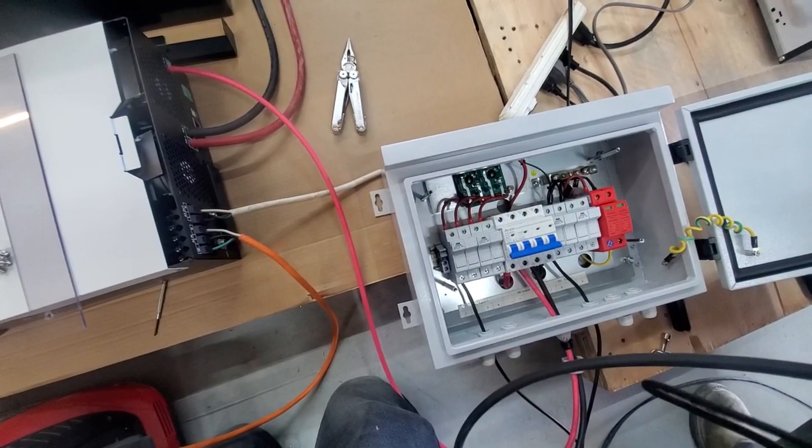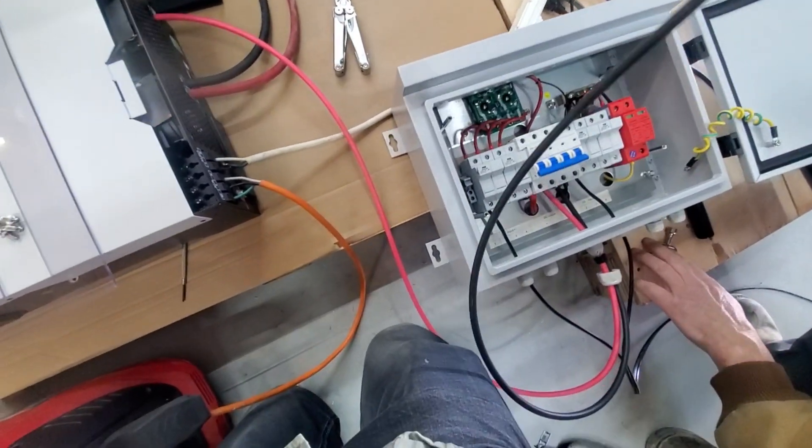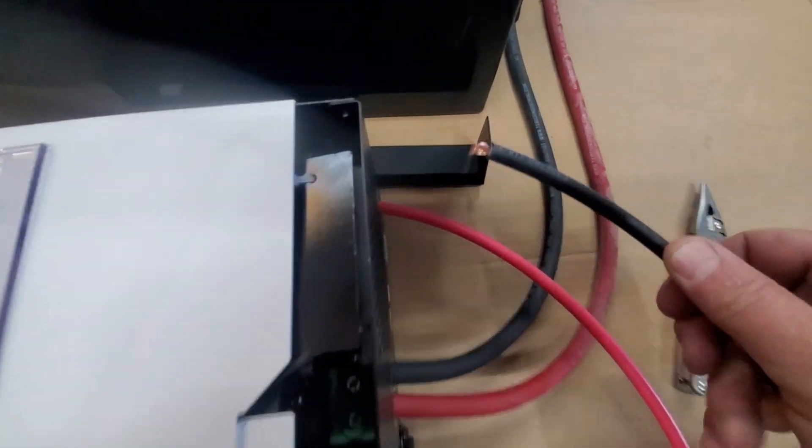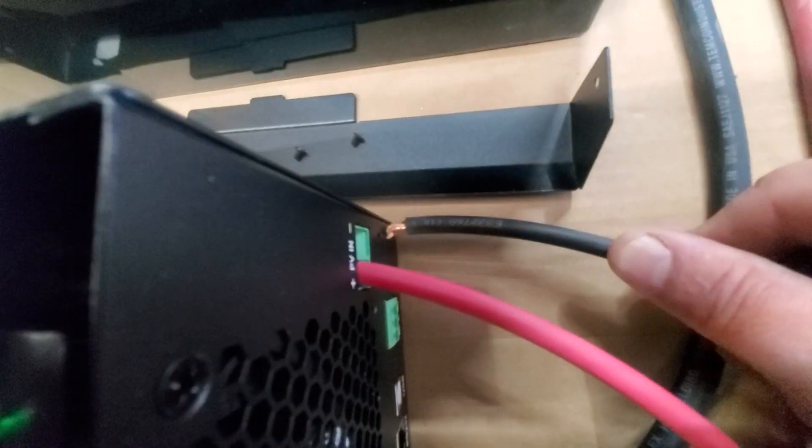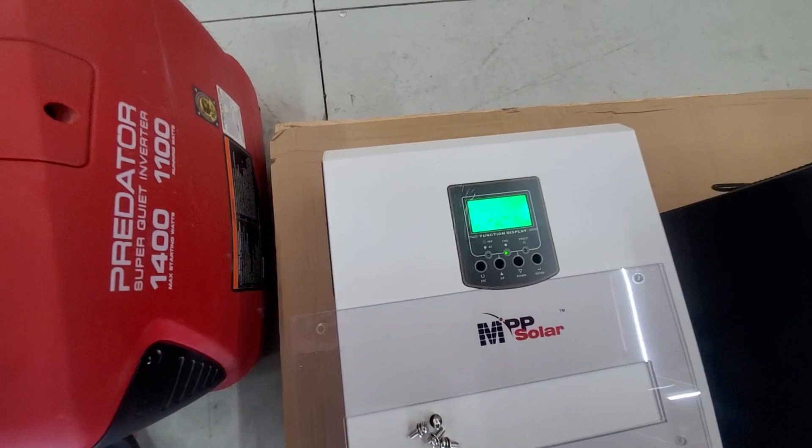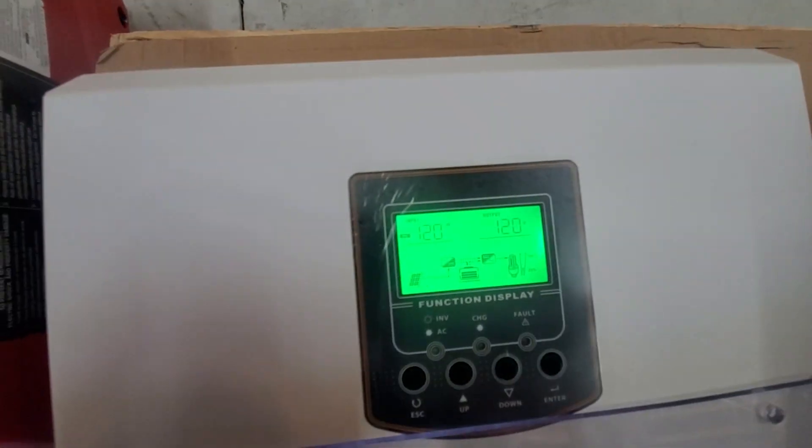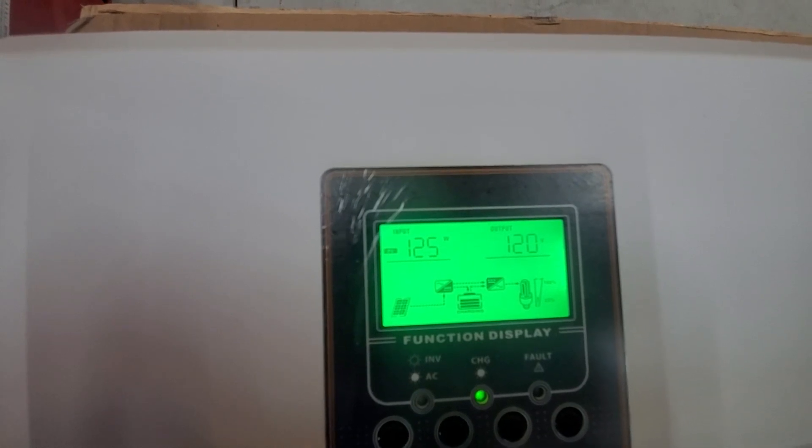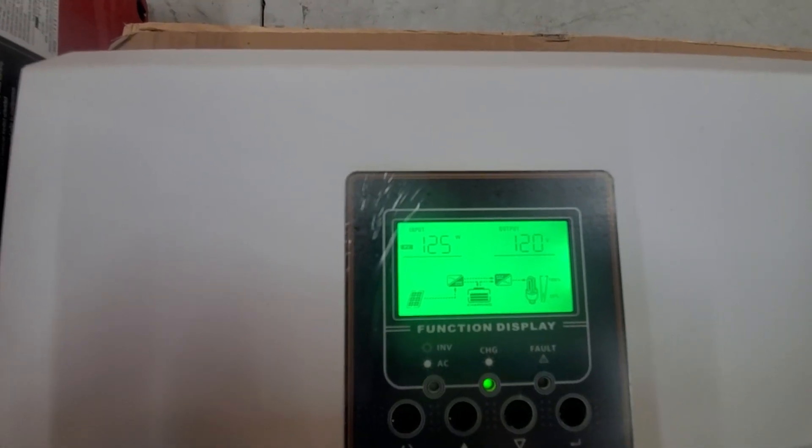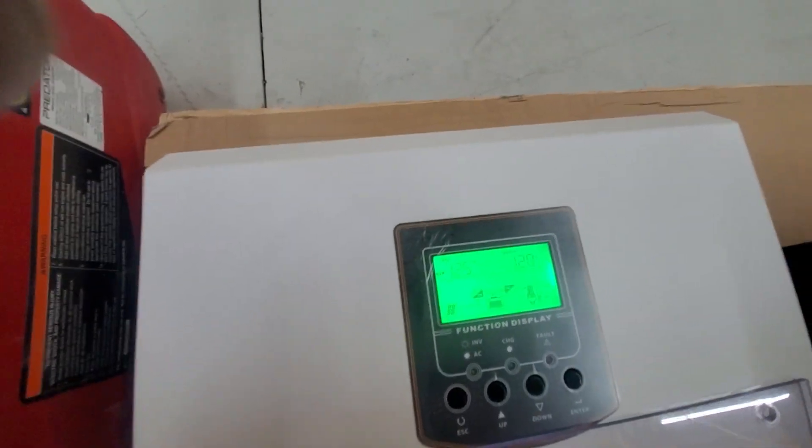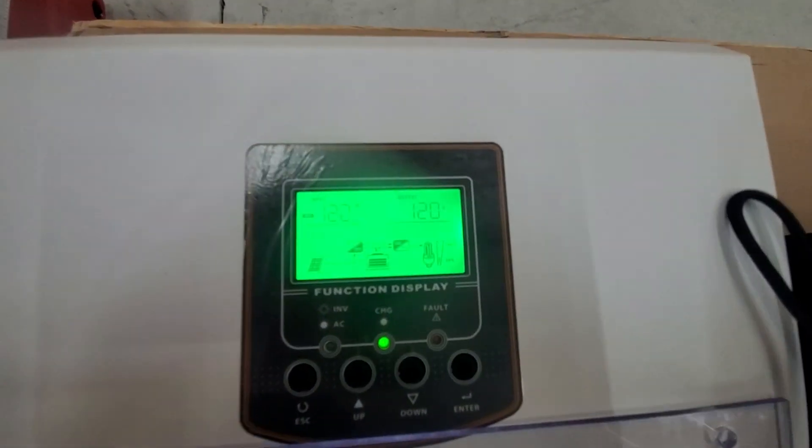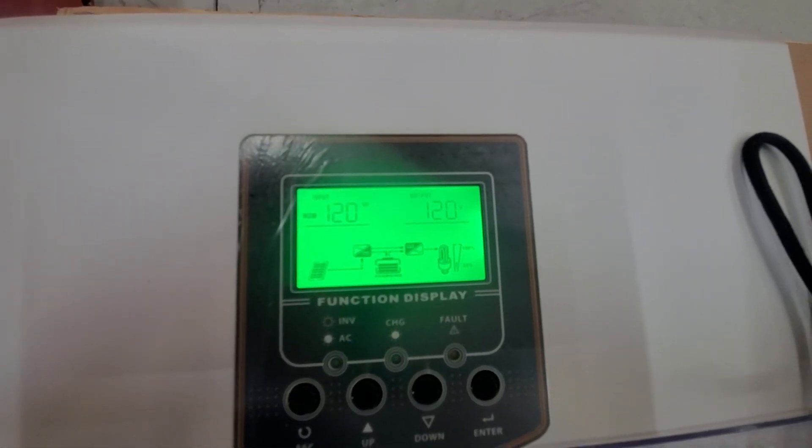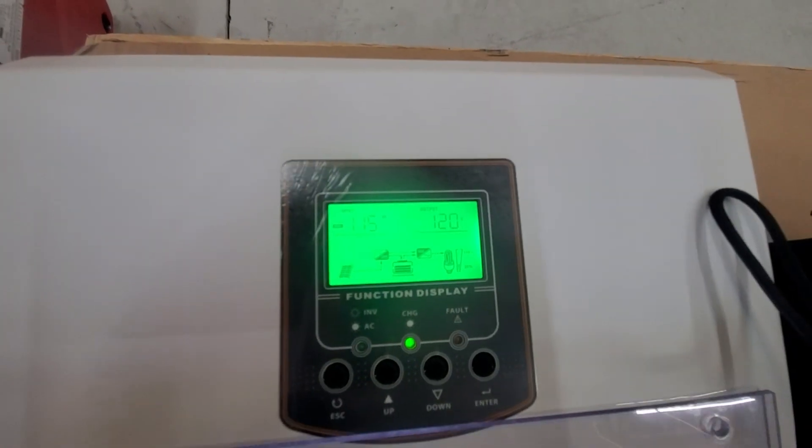Now adding a solar panel combiner box to show you how that works. We just basically wired it positive and negative on the output and that's going to wire straight in. We strip the wire, it's going to wire into the positive and negative input on the PV inputs. Sun has gone down a little bit, well a little bit behind the cloud, but we're getting only 125 watts out of our two 315 watt panels wired in parallel. We're kind of running at the edge as well. Like I mentioned before, you don't want to charge a 24 volt battery with something close to 30 volts or so. These two panels are in parallel, we're going to wire them in series and see what we get.